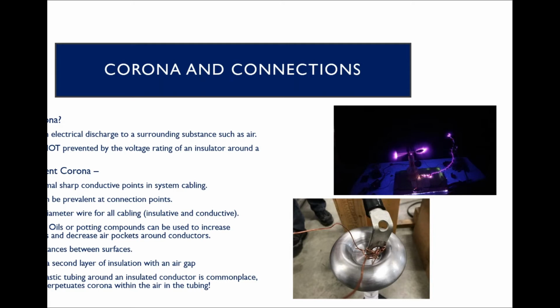So we're going to talk about corona and your connections with high voltages. One of the specific sources of error when working with high voltages is really due to corona. A lot of that is due to not understanding really what corona is or how it can affect your measurements. So what is corona? Corona really is an electrical discharge into the air that generates from the electrical conductor to the surrounding substance. So typically it's to air, but it can be to other gases or liquids even.